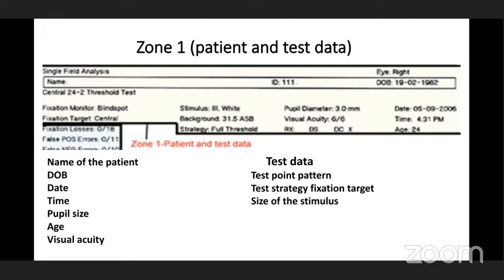In test data, we have the test point pattern — whether it is 30-2 or 24-2 — and test strategies, such as SITA fast or SITA standard. We also have the size of the stimulus, which should be size three. If there is poor retinal sensitivity, we can switch to stimulus size four or five.